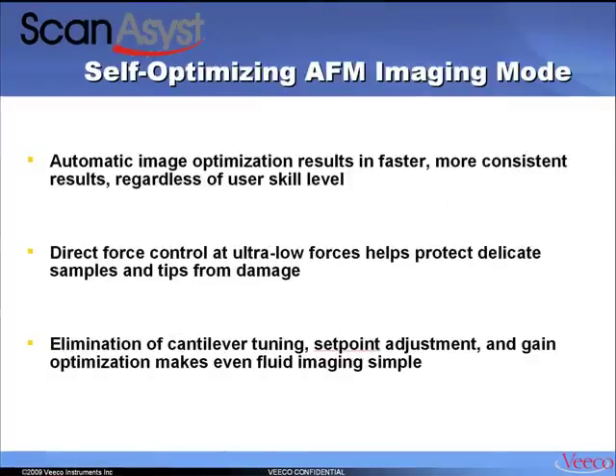To summarize ScanAssist: the automated image optimization results in faster, more consistent results, completely independent of the user skill level. Because of the direct force control used, ScanAssist can work at ultra-low forces, which helps protect delicate samples and tips from damage during imaging. And being a sub-resonant technique, cantilever tuning is completely eliminated, making it much easier to scan and even applicable to imaging in fluids. There is basically no difference from a user perspective between imaging in air and in fluids.